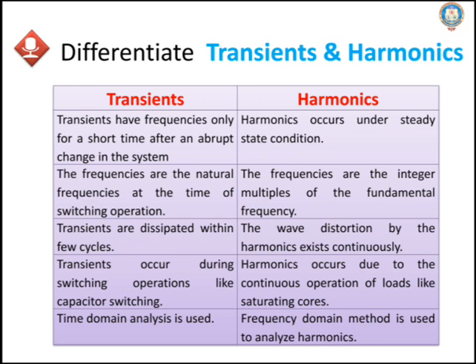Differentiate transients and harmonics. Transients have frequencies only for a short duration of time, whereas harmonics occur under steady-state conditions. The frequencies of transients are natural frequencies, while frequencies of harmonics are integral multiples of the fundamental frequency. Transients dissipate within a few cycles, whereas harmonics exist in the system continuously. Transients occur due to switching operations of capacitors, while harmonics occur due to continuous operation of non-linear loads. Transients are analyzed by time domain analysis, whereas harmonics are analyzed by frequency domain methods.